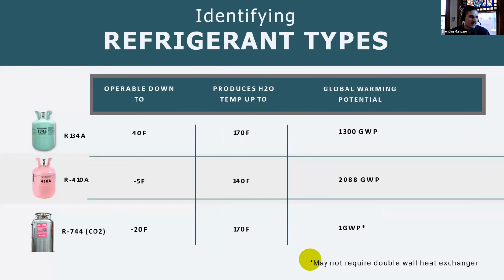Another thing I look at when designing these systems is the refrigerant types. There are 3 main refrigerant types in the United States right now that central heat pump domestic hot water systems will utilize. The first one is R134A. This can produce hot water up to 170, which is what we use as our target temperature for these systems, but they can probably go hotter, maybe 185 degrees. But they have a pretty high global warming potential, and when your project is looking at embodied carbon, that's definitely something to consider.